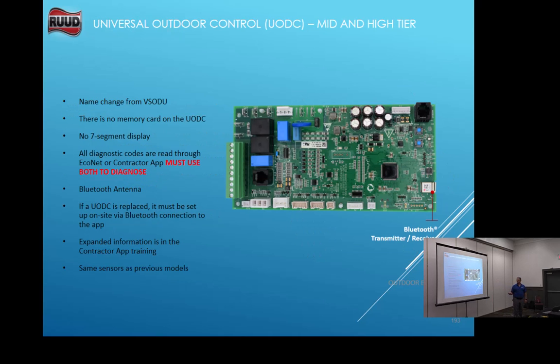When diagnosing these systems, if we have an EcoNet, you want to look at the EcoNet for diagnostics, and you want to look at your phone app for diagnostics. You may have some alarms in the phone app that you don't have on the EcoNet, and you could have some on the EcoNet that you don't have on the phone app. Now, if you have a 24-volt system thermostat, then you just go off what's on the app, right? But if you have both, you need to check them in both places, current alarms and history of alarms. And we never, never, never clear the history of alarms. Never clear it out. Leave it in there always.